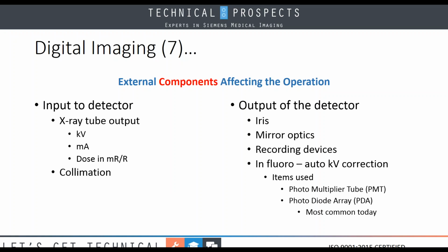The other thing to talk about here is the output of the detector. The iris: is it allowing enough light going to either the camera or the photo tube, depending on what you have? Mirror optics: is it properly directing the light to the appropriate device? Our recording devices all use low output signals in the digital world. Are we getting the appropriate factor? And then when we're in fluoro, we talked about this earlier, the auto correction circuit of either a photomultiplier tube or the PDA, the photodiode array, which is the most common today. One of the things that I would suggest to you is when you're doing your PMs out there, put different density material and make sure that this auto kV correction circuit works and works quickly.